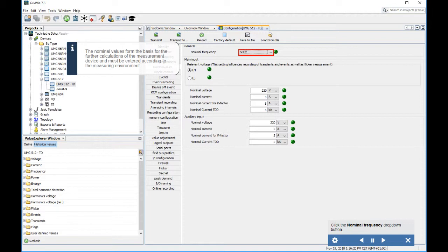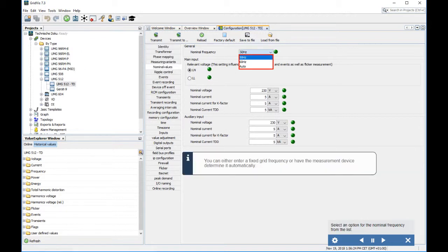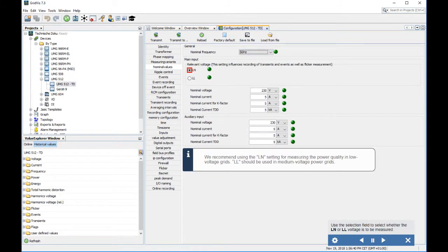Click the nominal frequency drop-down button and select an option for the nominal frequency from the list. You can either enter a fixed grid frequency or have the measurement device determine it automatically. We recommend using the LN setting for measuring power quality in low voltage grids; LL should be used in medium voltage power grids.